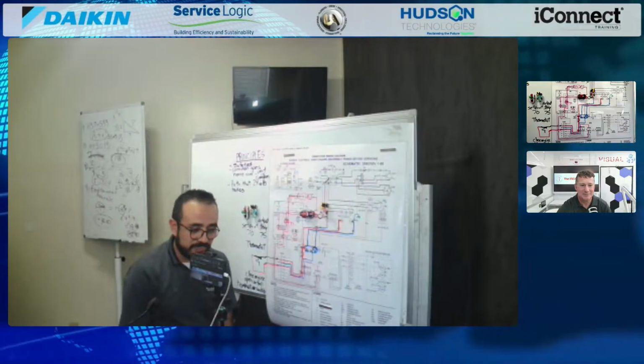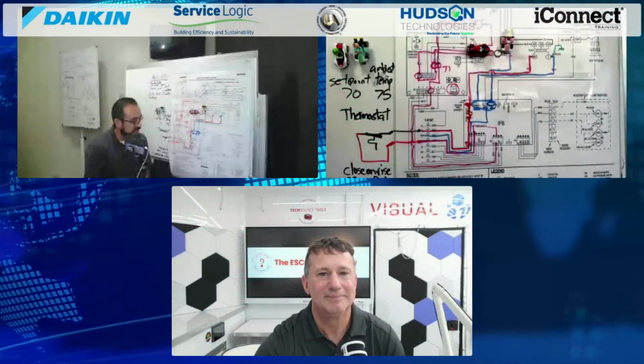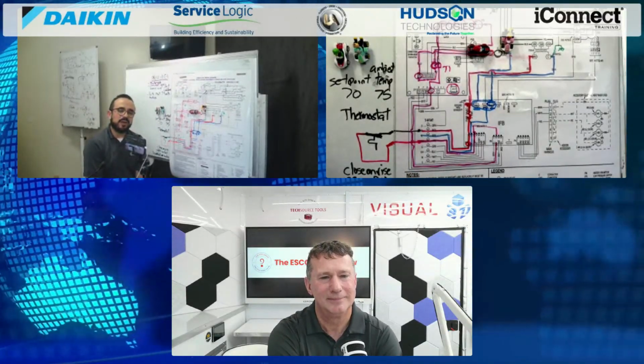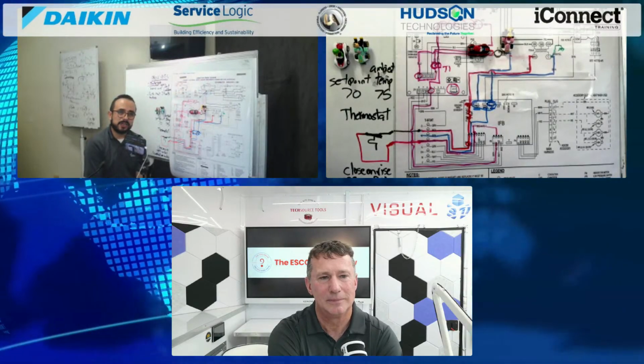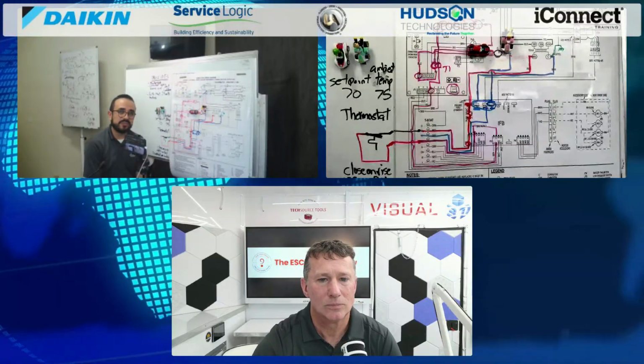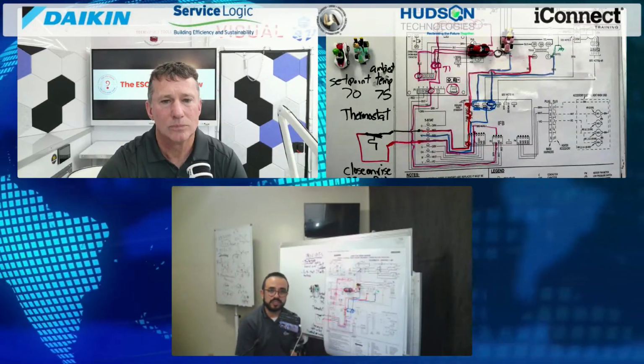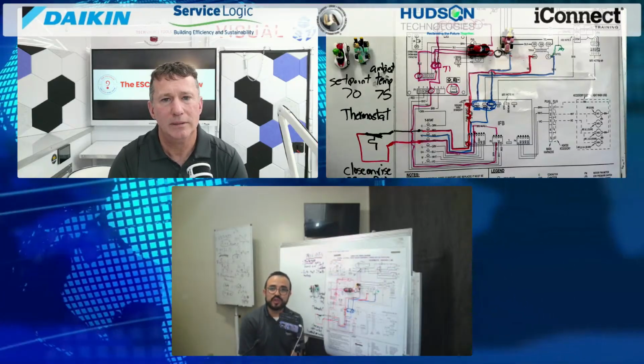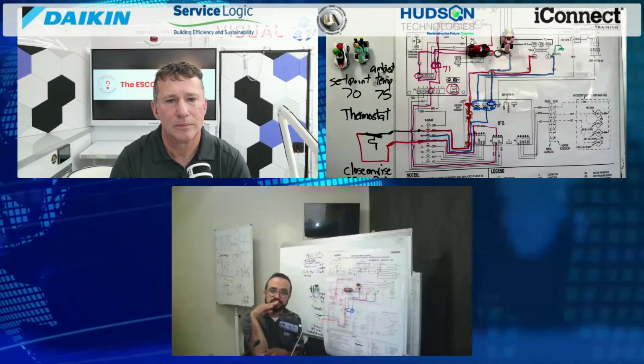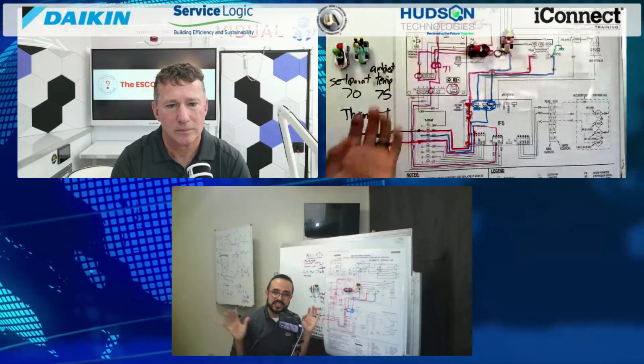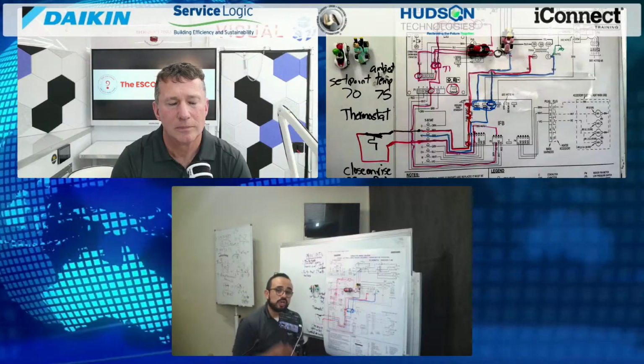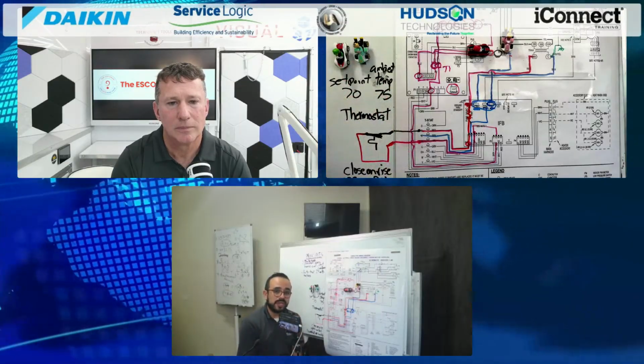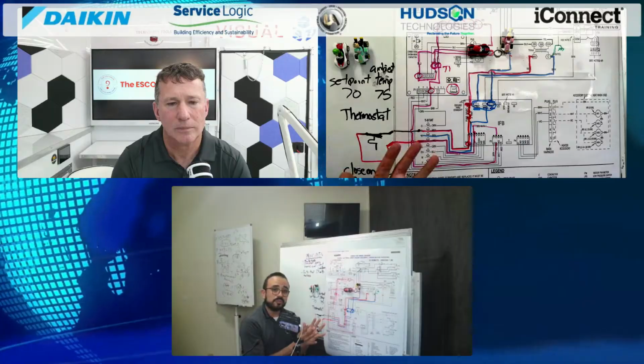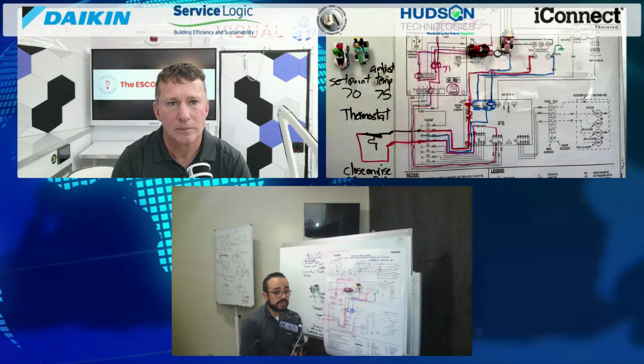I just tell them, guys, it's just a switch, that's all it is. Even with high voltage, you typically have the common, and it depends if it's single phase or three phase, but you have power already there. All you care about is for a little switch to close and make things turn on, that's all we're doing. And troubleshooting wise, I do tell them, have in mind that Mario and Peach have to make it to the contactor coil, because that's where they'll meet.